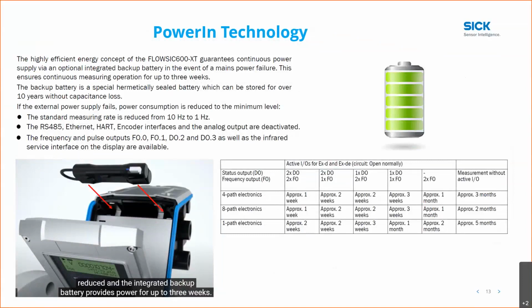Because of the low consumption of the SICK ultrasonic meter, you can actually run this off of a battery. So if you ever get a power failure or your fuse blows for some reason, if you opt for the battery backup, you will be able to continue running. Now, depending on how much I/O you are using in the meter will determine how long that battery will last. But as you can see here, an 8-path meter will last approximately 1 week with all the I/O active.